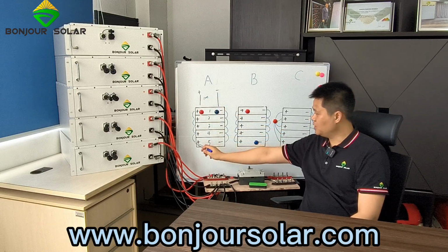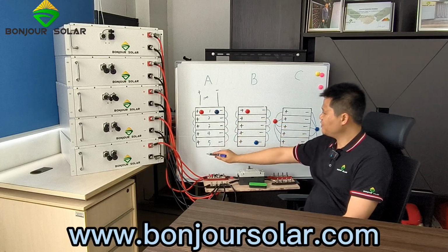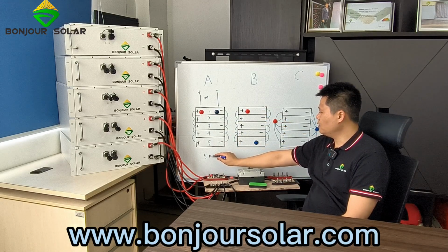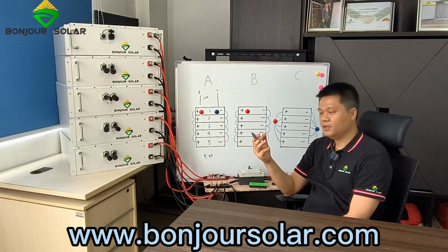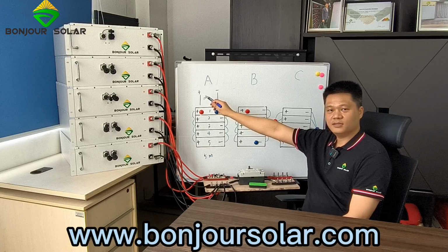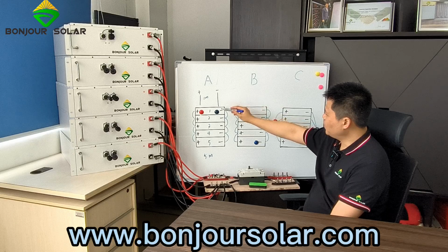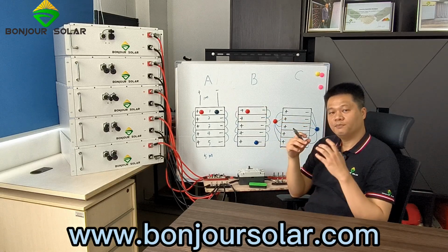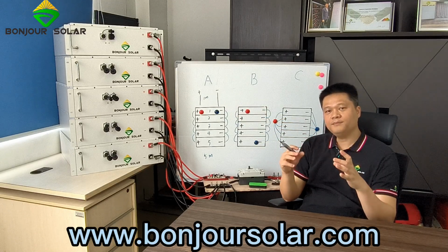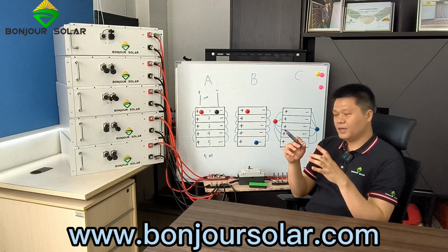From the inverter to the number 5 battery we have a 5 meter long cable, which is 5 times the resistance of the number 1 battery. So the number 1 battery has a lower resistance and the number 5 lithium battery has a higher resistance.